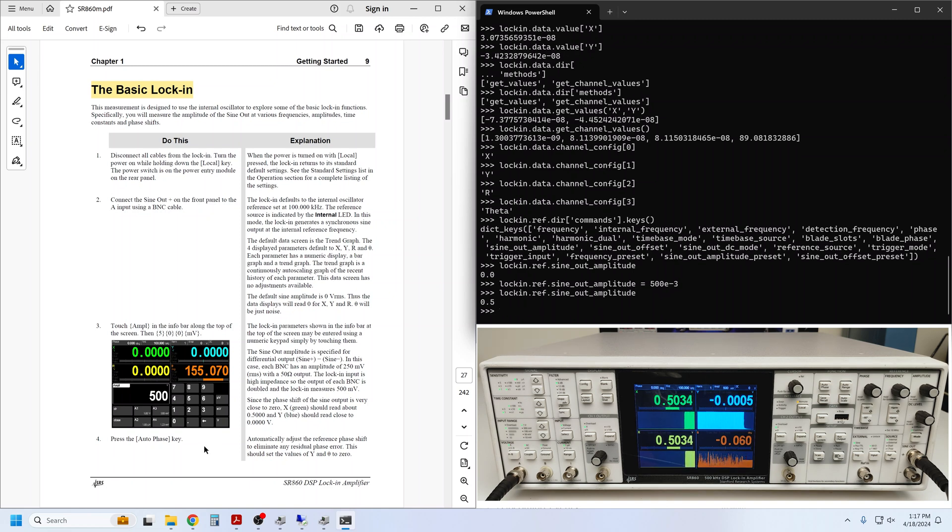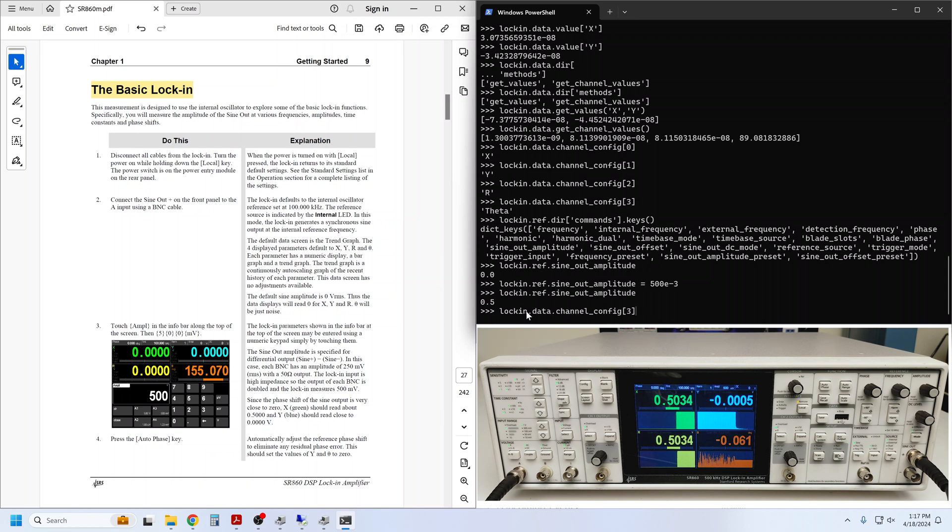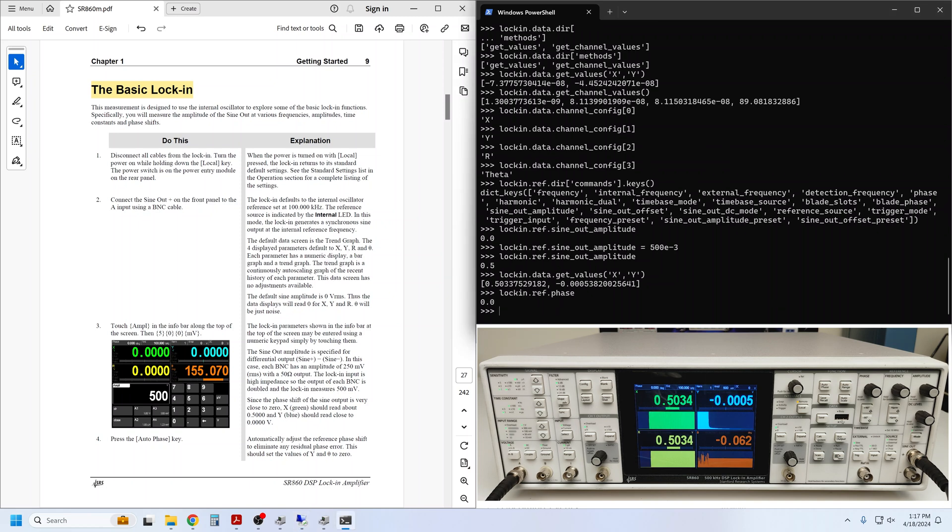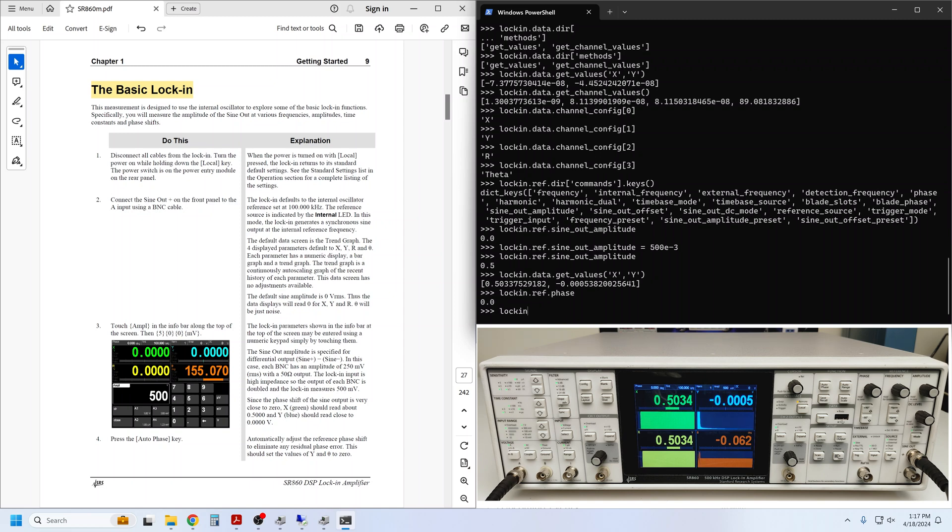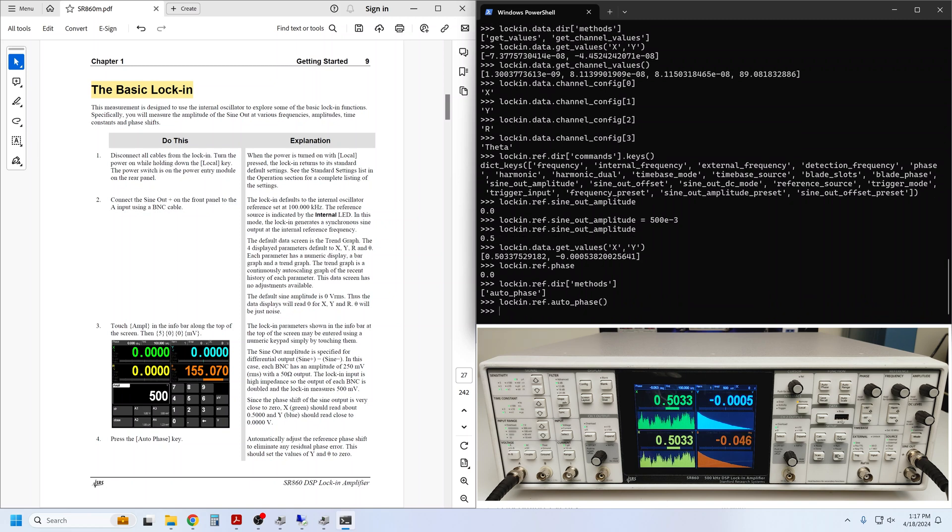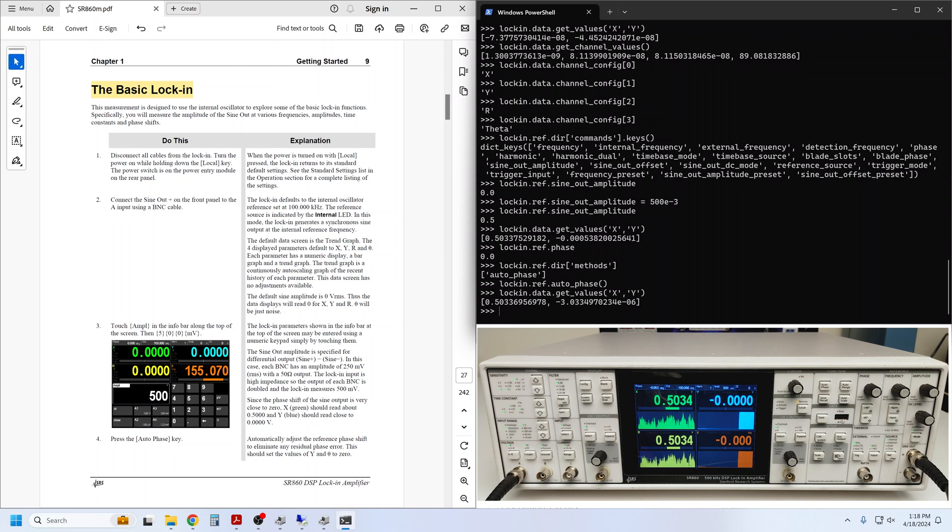Next, we are supposed to press the autophase key, but first let's query x and y now that we have a signal present. I can use the up arrow key to fetch recently sent commands in the terminal and get_values_xy. We can see that the 500 millivolt signal is present largely on the x channel, but there is non-zero y as well. Of course, by default, the lock-in phase is set to zero. Now we can go ahead and execute the autophase as instructed in the getting started guide. This is a method in the reference component. So I execute it simply with a set of empty parentheses. If we fetch x and y values again, we can see that the y component has reduced a bit.